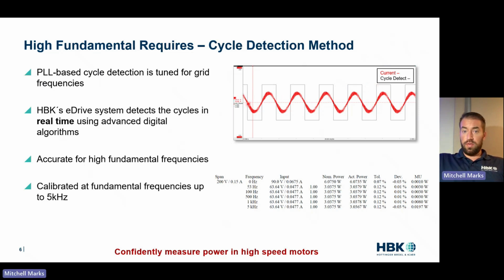So the HBK eDrive system uses a cycle detect method with our real-time algorithms. We filter the current or voltage, pick your favorite signal. We identify zero crossings, and then we average all the signals for electric power, for RMS values within each one of these time periods. This gives you a really high resolution measurement because you're averaging all these samples. It also makes it very dynamic because as that frequency is changing, you're tracking the frequency. And this is very robust as you go to high speeds, as you go to high fundamentals. As you can see from the values we have in our tolerances and our measured values, they're quite similar across the range. So the cycle detect allows you to be accurate at the high fundamentals because it's not looking for 50 or 60 hertz.